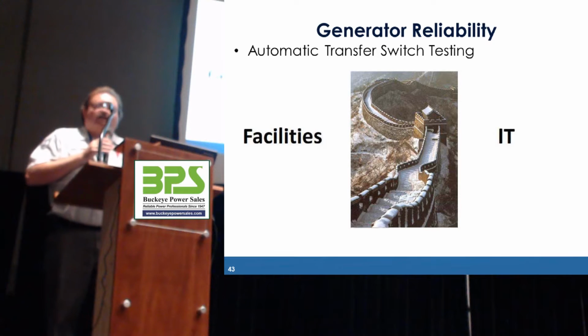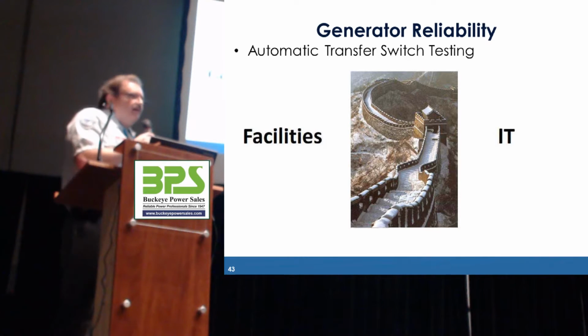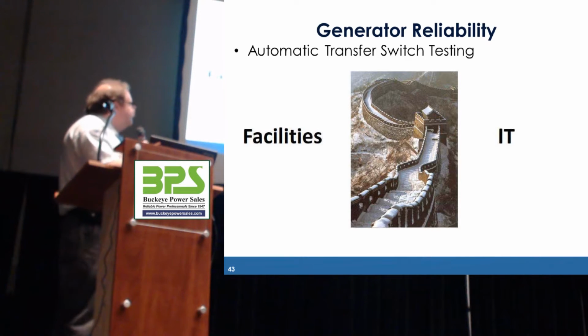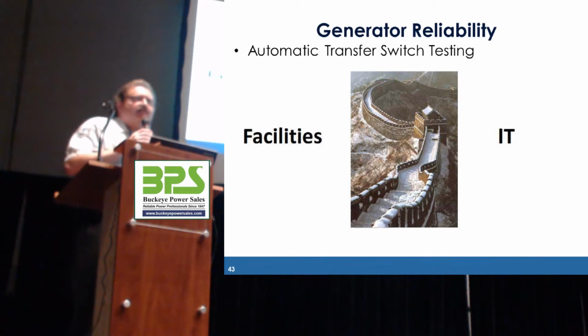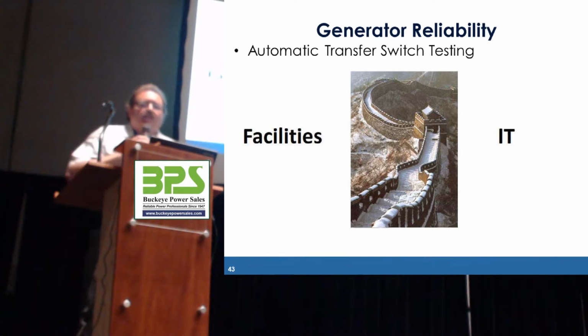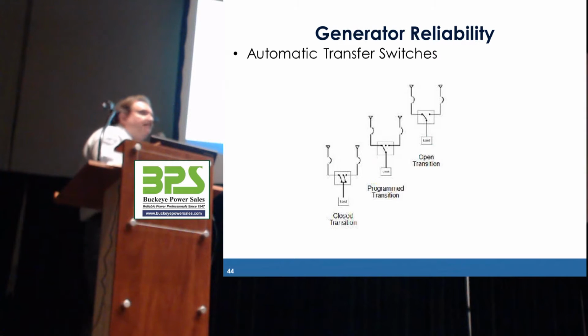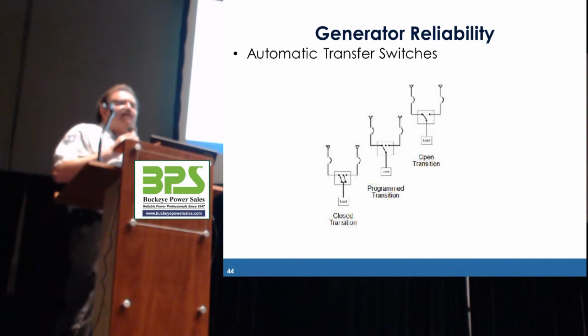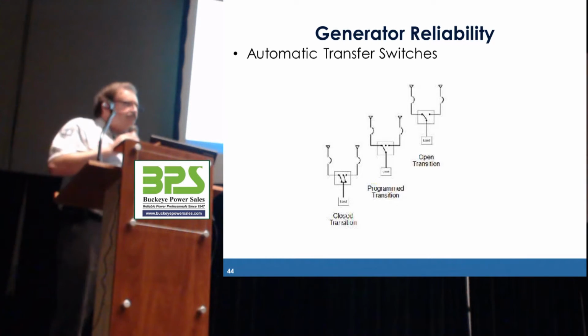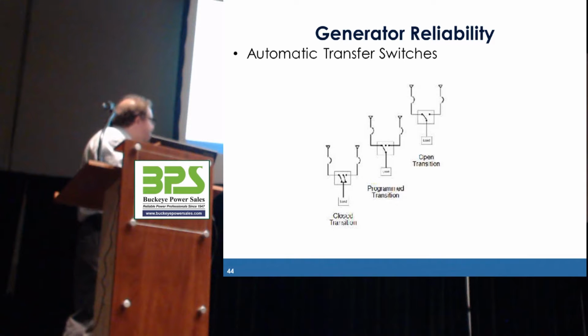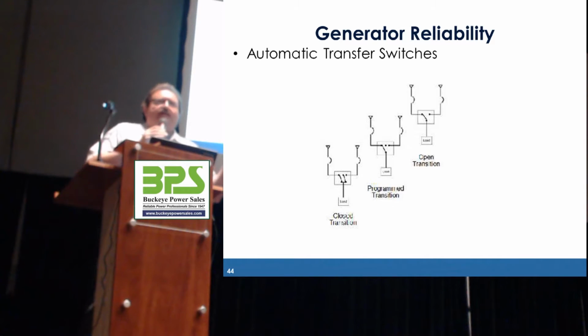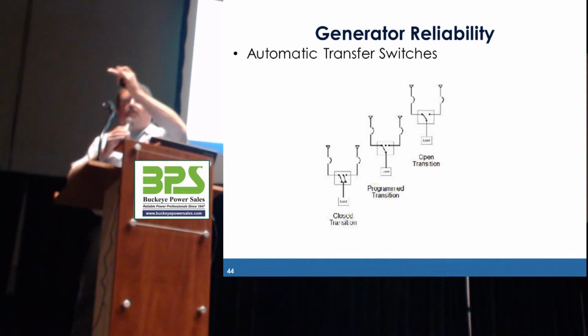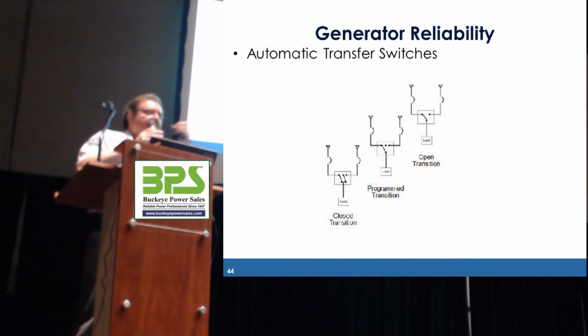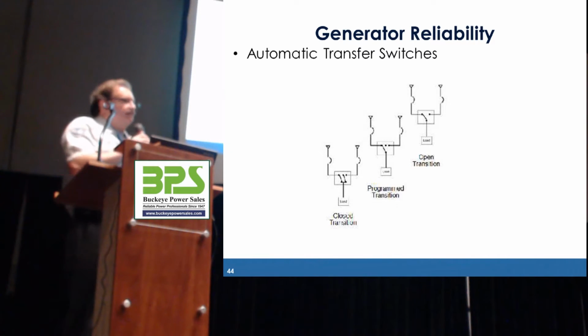Okay? We have to come up with a way of bridging that gap between facilities and IT to make sure that these can be done. And a lot of it has to do with the type of equipment that's specified. So if you have the opportunity to specify the equipment, there are different types of transfer switches. There's the standard one, which is just an open transition, which means we break from one source before we connect to the other source. So you've got a little bit of a blip when we're testing.